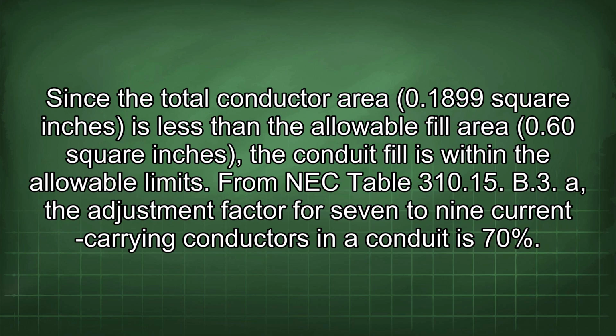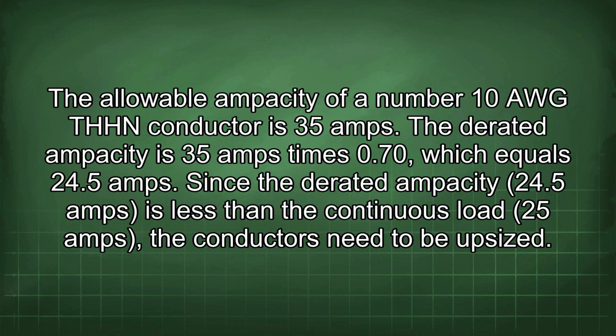From NEC Table 310.15(B)(3)(a). The adjustment factor for 7 to 9 current carrying conductors in a conduit is 70%. The allowable ampacity of a number 10 AWG THHN conductor is 35 amps. The derated ampacity is 35 amps times 0.70, which equals 24.5 amps. Since the derated ampacity 24.5 amps is less than the continuous load 25 amps, the conductors need to be upsized.